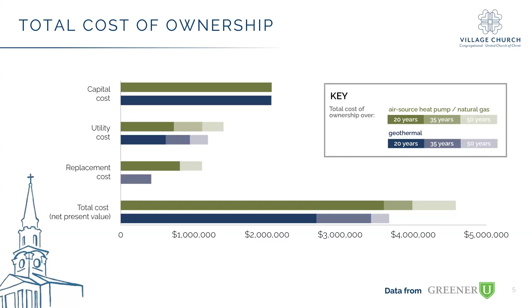Replacement costs are less, and this is what we came out with on utilities. And that turned out — we overestimated the cost of geothermal utility, the electricity we were going to use. I can't say for sure what our annual cost has been, but based on the first 4.5 months through this very cold winter, we're running about just under 30% electricity compared to last year with oil-fired boilers. That surprised us. We thought we'd be 30% over — instead we're 30% under the cost of oil-fired boilers and fans and everything you need to run.